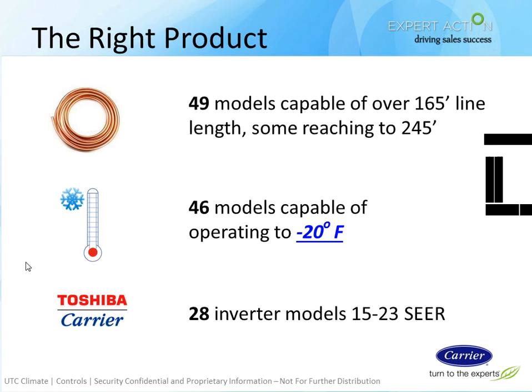Carrier is very strong in the commercial segment. For those applications that require long piping runs, we do have the ability to go up to 245 feet. And we have the unique ability to operate to minus 20 with some of our product here. While the rest of the industry has almost completely shifted to inverter-driven compressors, we see the need to have both options available to you. Inverter for high efficiency and comfort, and then fixed speed for those commercial applications that require cooling even in the middle of winter, and that would be our minus 20 Fahrenheit equipment.